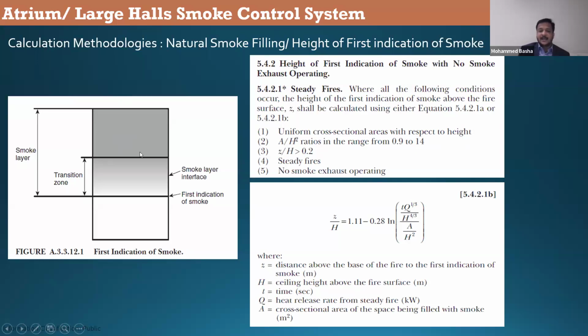What is A by H? A is the cross section of the smoke to be filled, this entire cross section. H is the total height of your particular floor or an atrium. And Z by H shall be greater than 0.2, which is the tenable height versus the total height of your particular floor. Steady fires. This formula is only for steady fire.